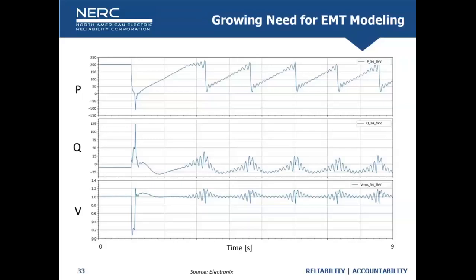And the question becomes, how do we know when we need to study those in more detail? Because the positive sequence simulations fall short in a lot of cases. They either don't converge or they give results that don't match reality, mainly because there's a lot of complex controls built into these resources that aren't modeled in the generic positive sequence simulation tools. So this is a good example of a voltage excursion, a fault event, looking at whether the resource provides sufficient ride-through capability during the interconnection process. It's not shown here, but the positive sequence simulation tool showed a very stable response. The fault occurs, the unit responds, comes back to pre-disturbance output in a couple hundred milliseconds, and off we go.